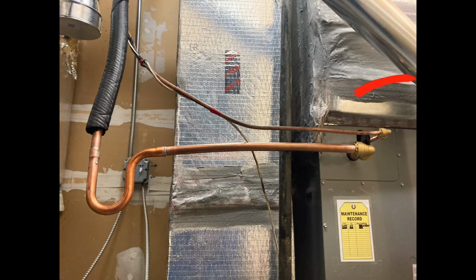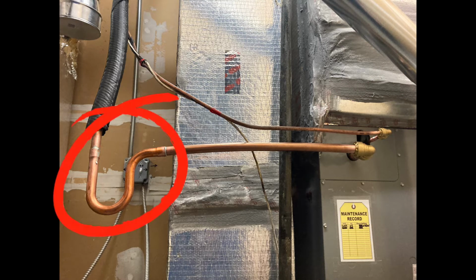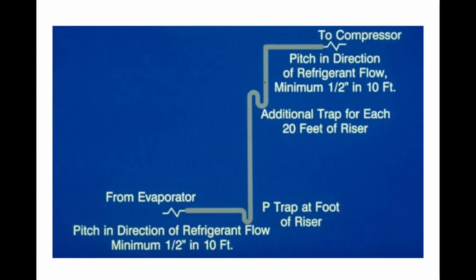That's what it kind of looks like installed. Use those Zoom lock fittings on the right-hand side here. That P-trap you see is to trap oil when the system shuts off because we have such a tall, long line set going up to the roof. We don't want to flood our evaporator with oil when the system shuts off.